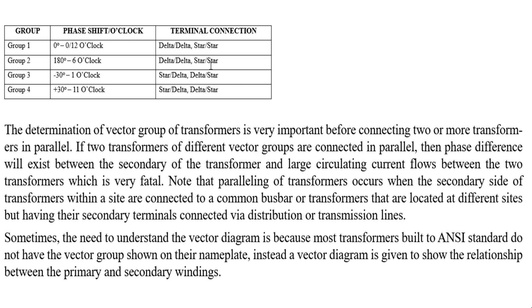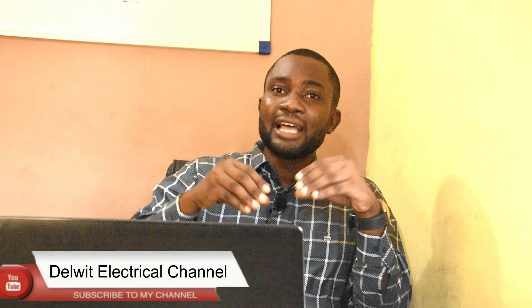These things are very important in our discussion on vectors of a transformer because the technicality would be triggered if you don't understand these basics. Please notice that if you don't understand the vector group and two transformers are connected in parallel, a phase difference will exist. When that phase difference exists, you might not understand how the circulation of current will grow — you will see a large current flowing between the two windings, and it might damage your transformer.